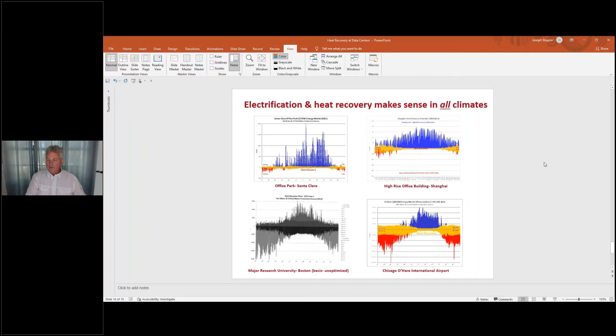Now I'm helping design the system for new terminals at Chicago O'Hare Airport, shown in the lower right. Again, in that cold climate, they can still meet 50% of the annual heating demands just by recovering waste heat from cooling that they're currently throwing away.